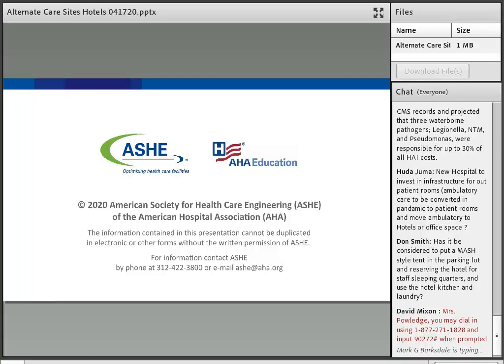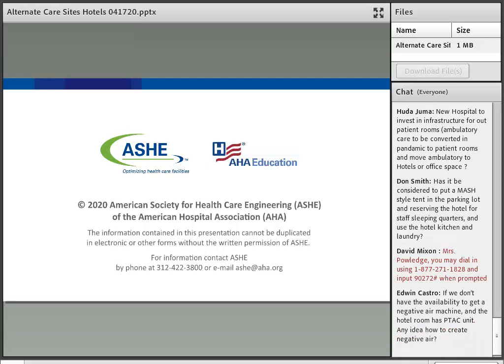This is a concern not just in hotels, but any vacant building right now during this massive quarantine. Schools, office buildings, it is a major concern, and some facilities are addressing it by having people on staff to make sure that there is not all of this stagnant water and the water treatment is ongoing. We know that's not occurring. So one of the recommendations we're making is when they open up the economy and open up these types of facilities, you've got to do some type of water test. And in the worst case, you may need to flush your entire domestic water system in order to get some of those pathogens out. It really is about preparing for it, putting measures in place, and being aware of it, but we know that that is a major concern.